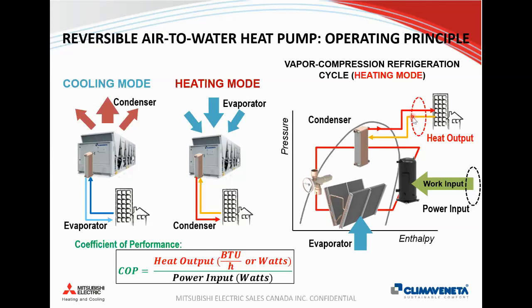They can have, depending on the conditions, much higher COPs, anywhere from 3 to 4 or 5, depending on the system type and of course the conditions. But this class of heat pump typically will have a minimum COP of 2. So if we're comparing that to a natural gas boiler that's operating at an efficiency of less than 100%, then from a pure energy point of view, that can make a lot of sense.